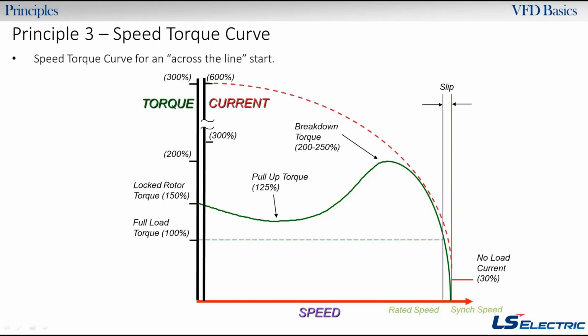And the difference between your synchronous speed, which is the rotating magnetic field in the motor, and your mechanical rotating shaft is going to be slip. So if you look on a nameplate, you see 1750. Well, that's 50 RPM of slip because it's 1800 RPM minus 1750. So if you're at no load, you're typically at like 30% rated current. But if you start loading down that motor, so let's say you have a conveyor and you keep adding rocks to it or some kind of product, you're going to start adding more slip.